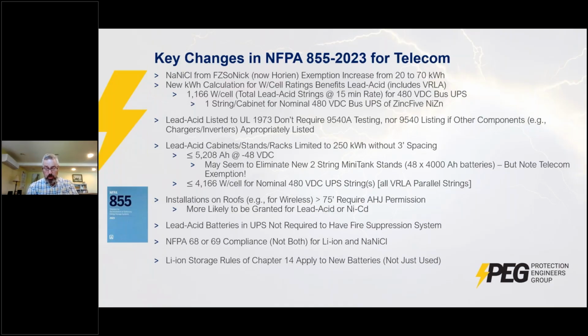There's really no limitation, but there is wording. You could misread the code and say you can't have 2 large tanks of telecom batteries next to each other. 48 4,000 amp hour batteries would be over the 250 kilowatt hours, but telecom has an even broader exemption, so you have to make sure that's being employed and that the AHJ understands that. There's no limit in the size for telecom. In addition, that's 4,166 watts per cell for a nominal 480 volt DC string with all the strings parallel. So there are limitations on how large the systems can be and how closely they can be spaced together.